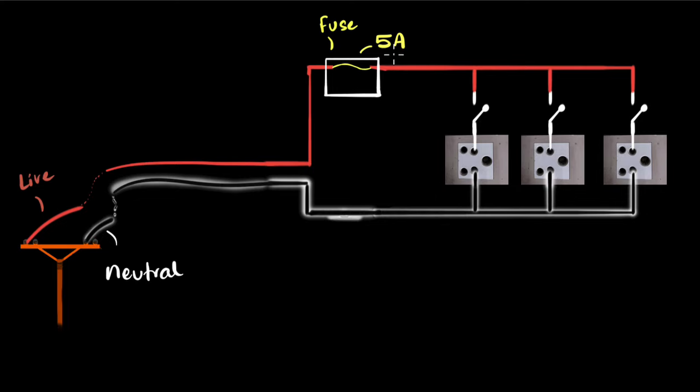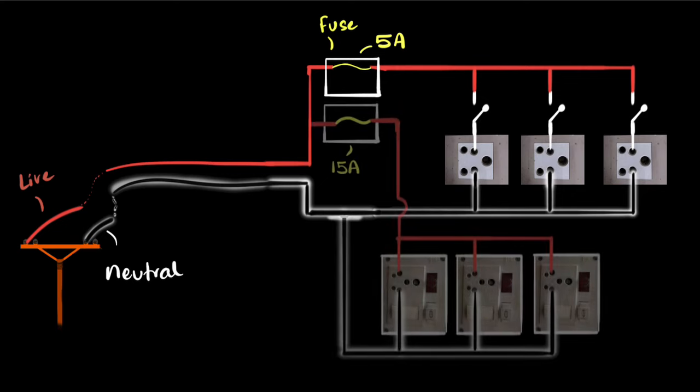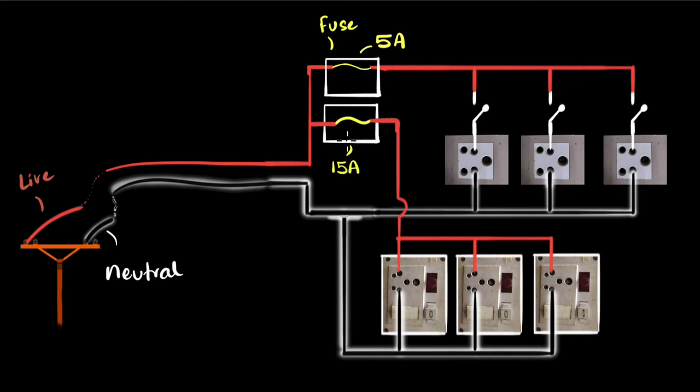Why 5 amperes? Because most appliances don't need a lot of current. But what about your refrigerators, geysers, air conditioners? They definitely need a lot more current. So for them we will build a separate circuit. Can you see, I now have a separate parallel circuit over here with a much higher fuse, say 15 ampere fuse.